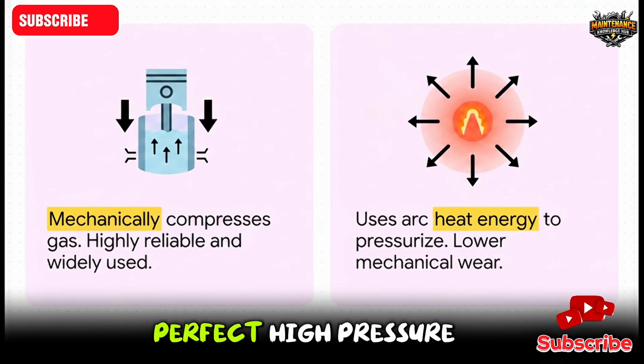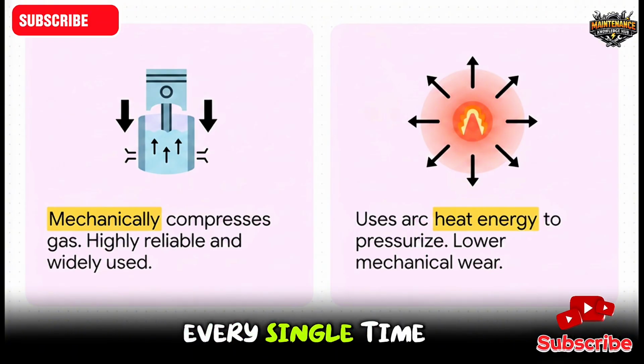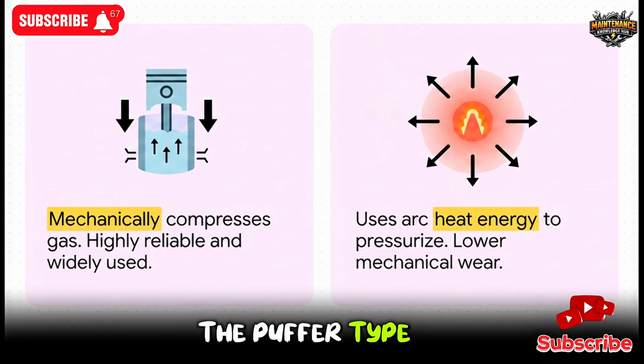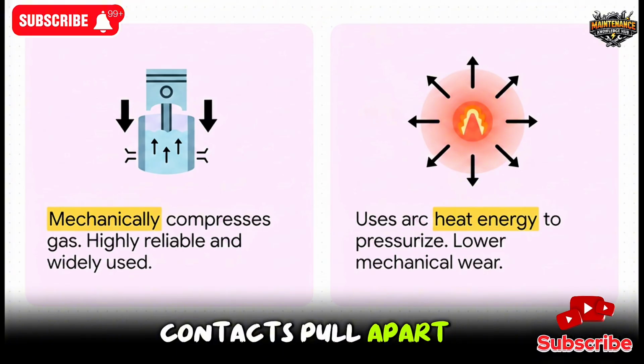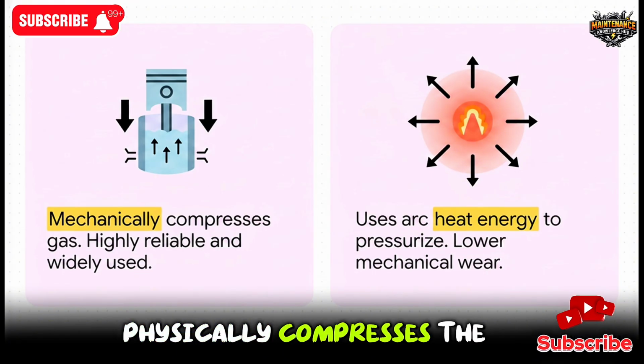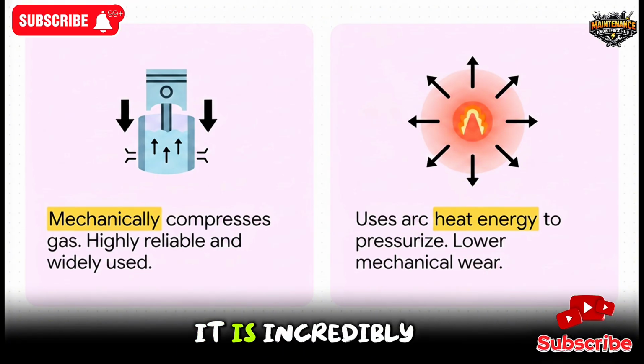Now let's transition over to Section 4, Types and Testing. So to achieve that perfect high-pressure gas blast every single time, engineers generally rely on two main designs, the puffer type and the self-blast type. The puffer type is your traditional powerhouse. Basically, as the contacts pull apart, a mechanical cylinder physically compresses the gas to create the blast. It is incredibly reliable and by far the most common.